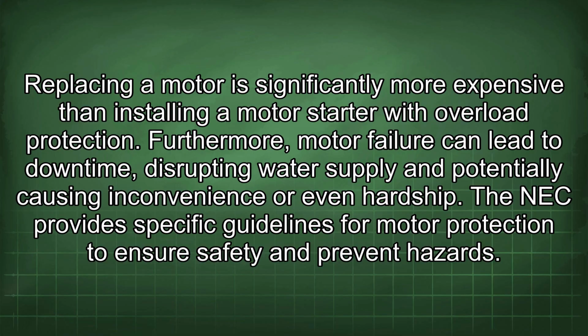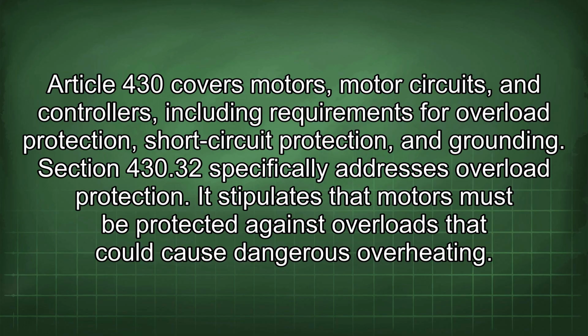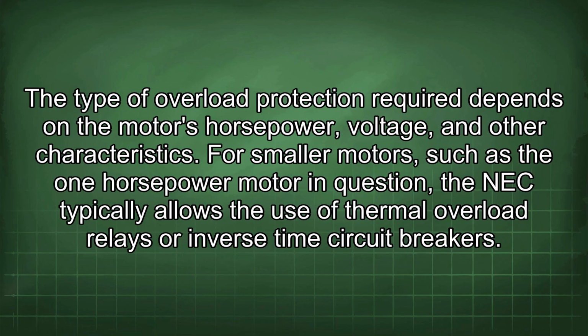The NEC provides specific guidelines for motor protection to ensure safety and prevent hazards. Article 430 covers motors, motor circuits, and controllers, including requirements for overload protection, short-circuit protection, and grounding. Section 430.32 specifically addresses overload protection. It stipulates that motors must be protected against overloads that could cause dangerous overheating. The type of overload protection required depends on the motor's horsepower, voltage, and other characteristics.